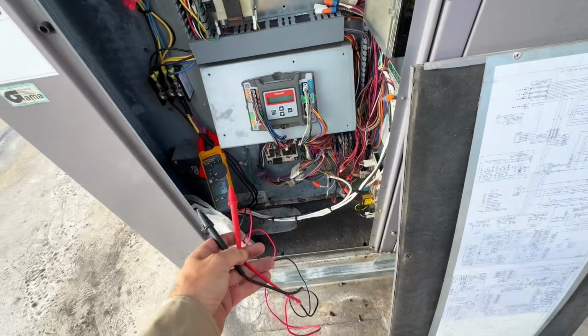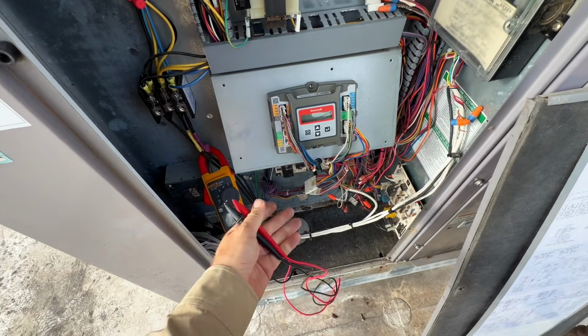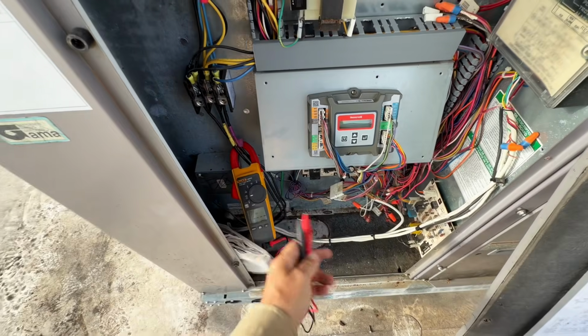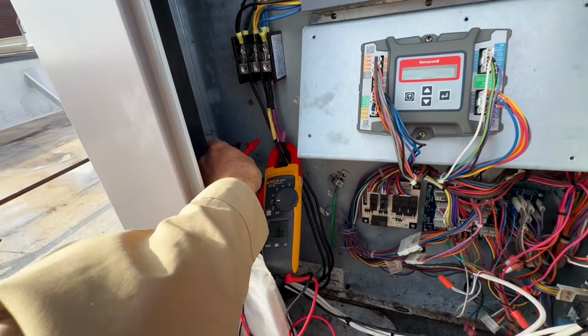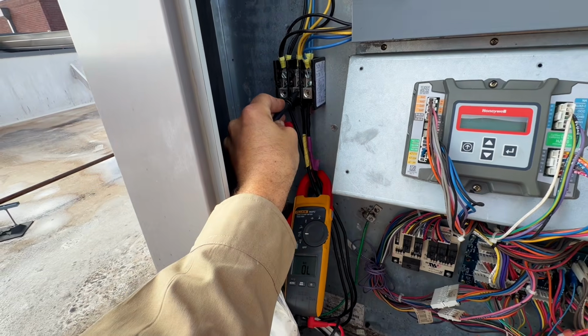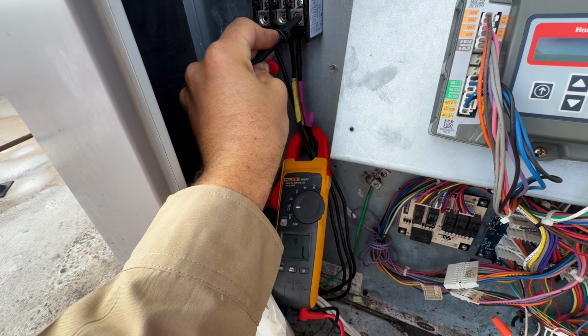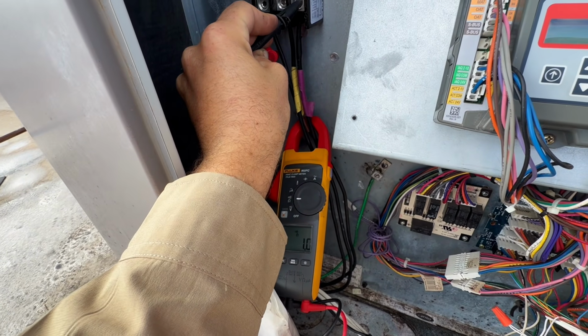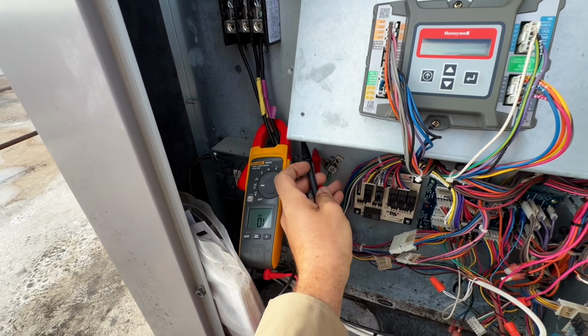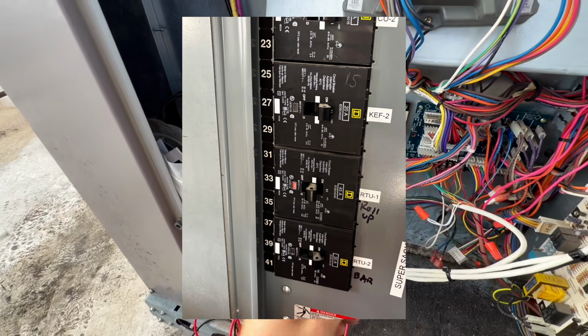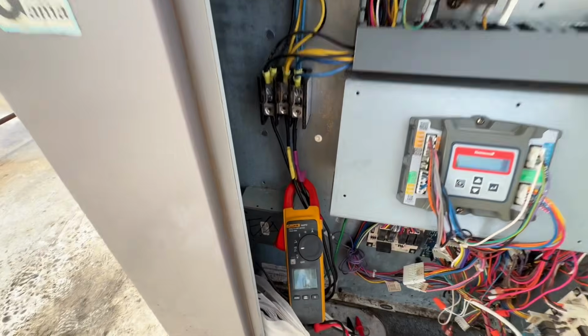So before I reset the breaker, I always want to make sure that I don't have any components that are damaged or any components that are shorted to ground. I went through here and you can see we don't have anything here, but then look at this. So we have 1.0 ohms from this terminal to ground, which obviously will cause our breaker to trip, because that's not what we want to see.